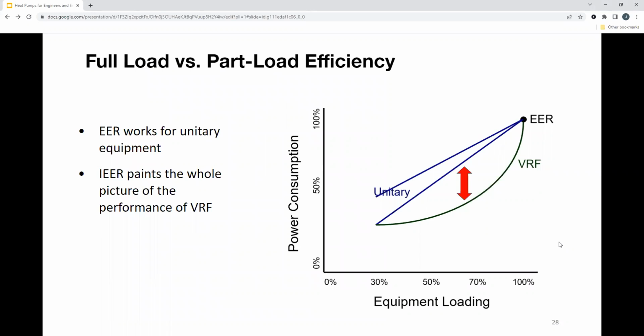And I know Alex has mentioned this briefly, but I just wanted to show you what I'm talking about here. EER values are not the best for heat pumps, and it's because it's at full load demand. So 100% loading, and it's going to be about 100% power consumption that it's tested at, right? If you're looking at unitary equipment, EER is a good rating because it is very linear as it goes up and approaches higher capacity and more power consumption. IEER is there to show that VRF curve that we're seeing, right? And assuming that around 70% load, we're actually below 50% power consumption, where the unitary system is going to be at 65, 70% of that power consumption. So IEER really paints the whole picture of the performance of a VRF system.